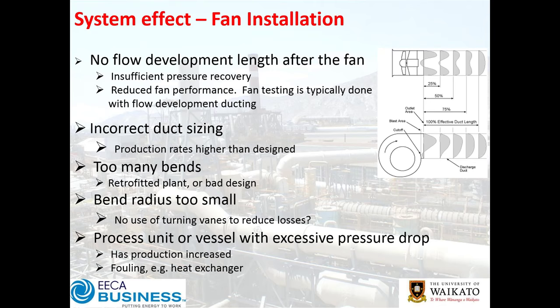Process vessels may have excessive pressure drop — perhaps because production has cranked capacity up, or a heat exchanger has heavily fouled over the years. These things happen, and in running and operating a plant there should be a strong emphasis on keeping an eye on critical process metrics. Static pressure drop is a really cheap, easy variable to measure and track, with alarms and trigger points. As you learn to know your system, you'll quickly identify those one or two bad actors to follow up with.